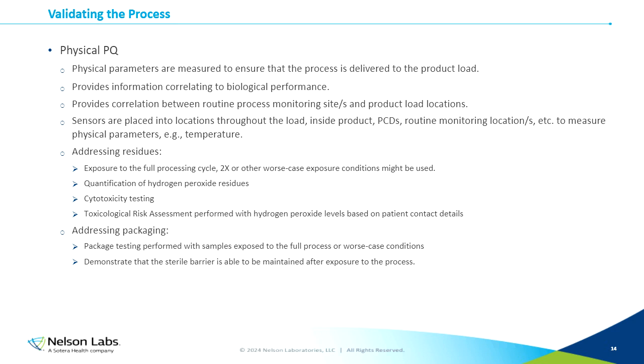We also need to take a look at physical performance. So we also perform a physical performance qualification when we validate these processes. This is where we measure physical parameters to ensure that the process is delivered to the product load. This physical performance qualification provides information correlating to microbiological performance. If we see physical results that do not confirm the microbiological results, then we would want to look into those to figure out why that is the case.